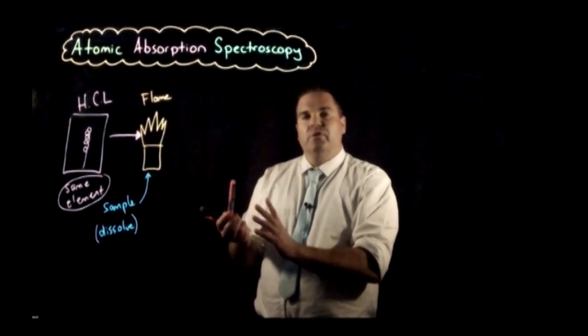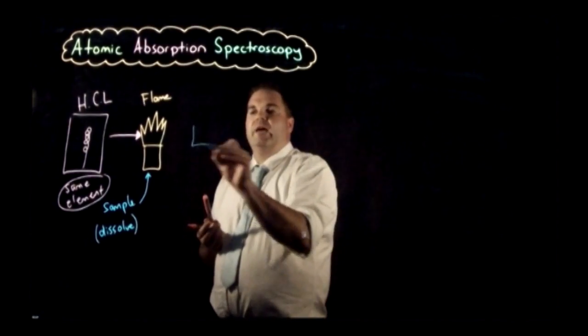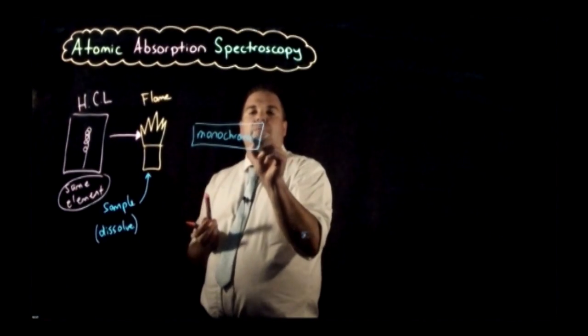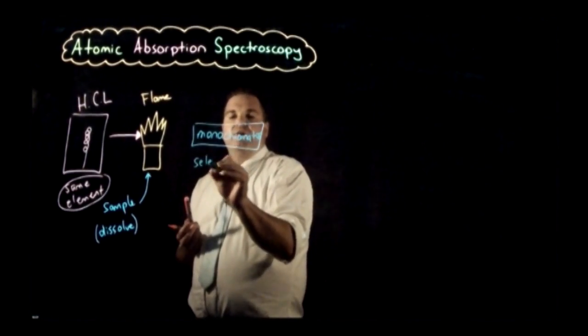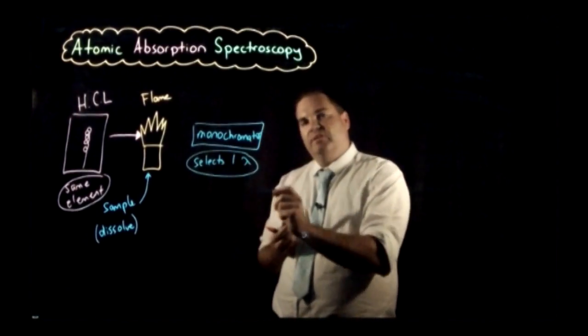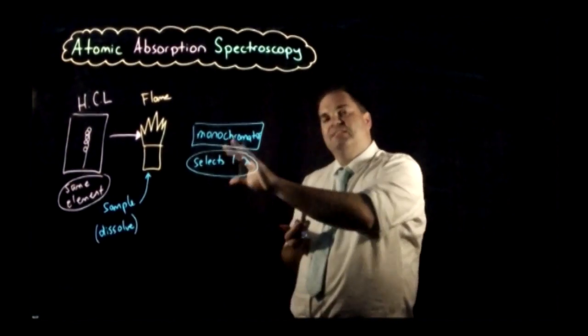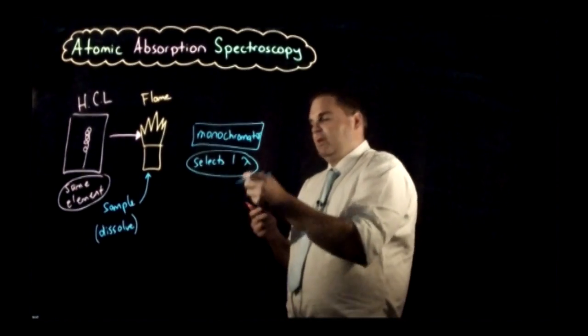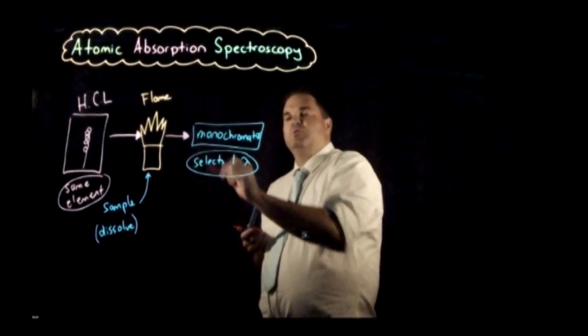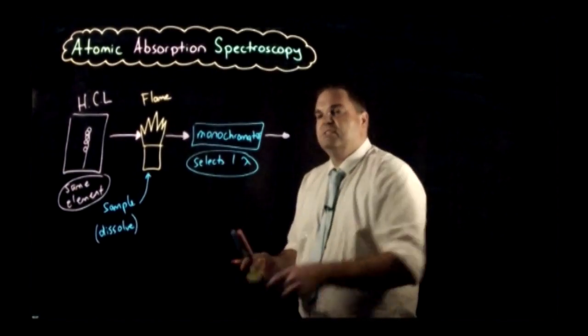There are all different forms of light around because of visible light, so the next component is something called a monochromator. A monochromator selects one wavelength. So the wavelength we're trying to measure for our specific element is selected through the monochromator. The sample comes through, some of it gets absorbed in the flame, and the monochromator selects which wavelength we're actually measuring.